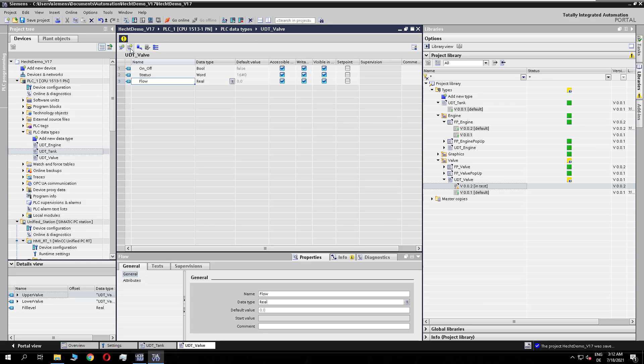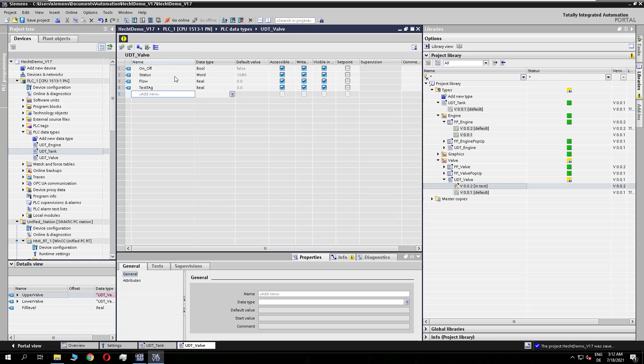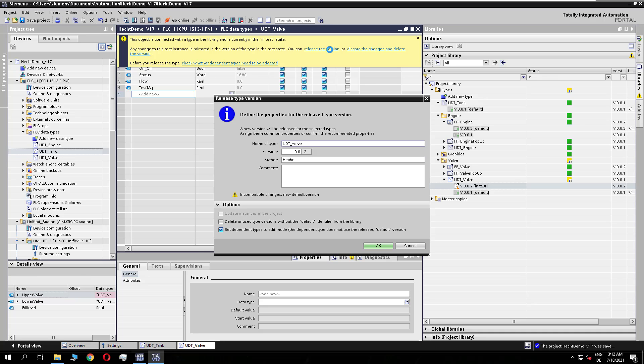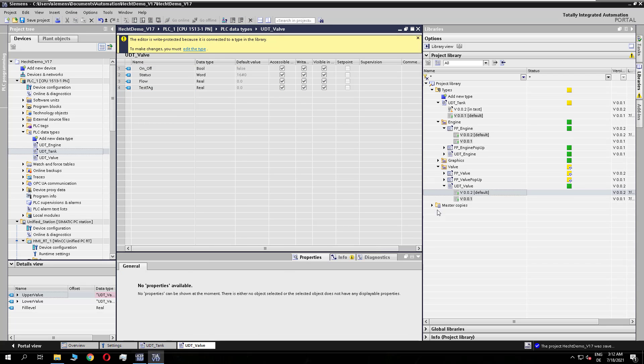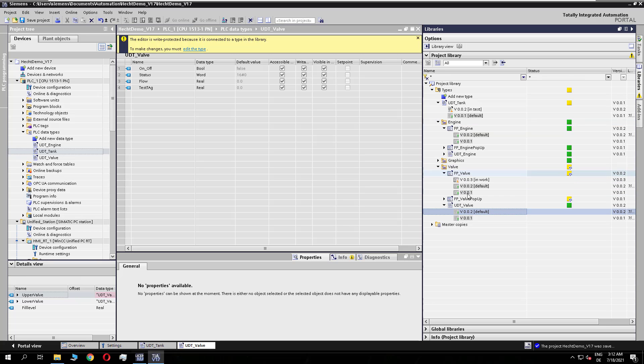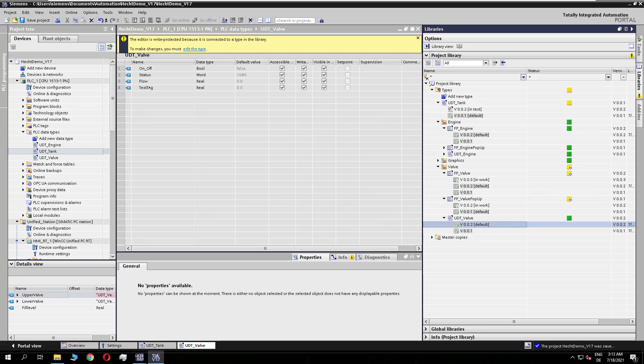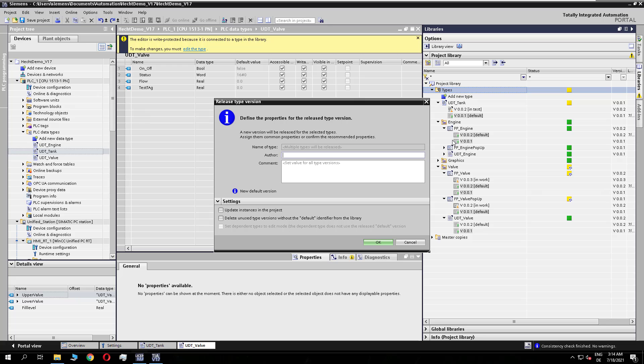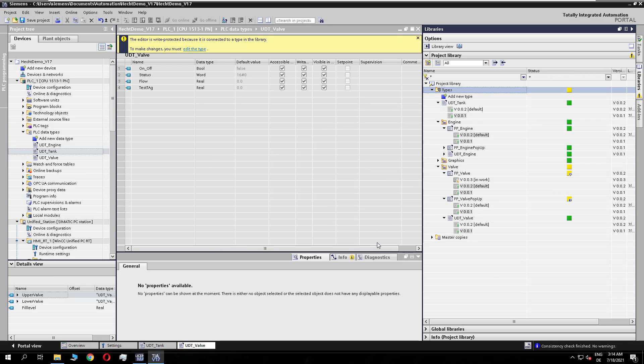Now I do the same thing but instead of adding a comment, I change the data structure — for example I add a new tag. When you release this version, you see that the UDT tank also goes into test mode, because this was not just a comment but a data structure change, which needs a version adjustment. The face plates are also in work, so we have the possibility to say 'release all' and we're done.